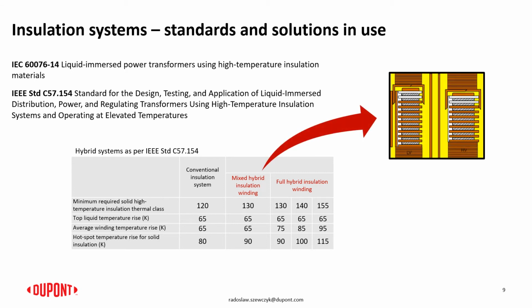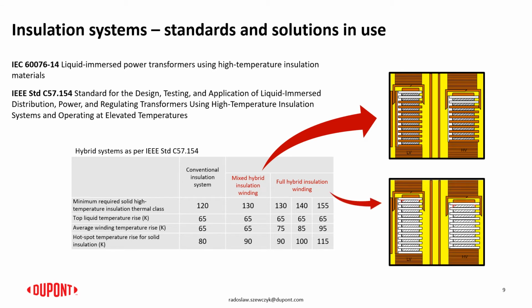So, for example, here we have the guidance for something called mixed hybrid insulation system, where we have a portion of the winding insulated with the Aramid insulation. This is the white part of the winding shown on the chart. Or we could have a hybrid insulation system, or what we could call full hybrid insulation system, where the entire winding, including the conductor insulation, the spacers, is insulated with Nomex, while the parts which are in the distance from the hot conductor could be insulated with the cellulose.